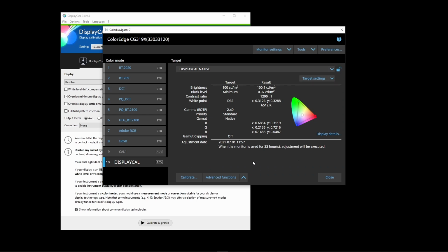What that allows us to do now is go and profile using DisplayCal, then load the LUT using a function called Look View LUT in Color Navigator 7. That's really designed, I guess, to load if you had an S-Log or V-Log or Log C from an Arri Alexa type camera, to make a look-type LUT and load it into the system, since this can already be calibrated to Rec 709. But this slot is also inline in the color pipe, which we use for creating a 3D LUT for calibration of the monitor. Once we've done that, we hit the close button and it'll close out and unlock the monitor.